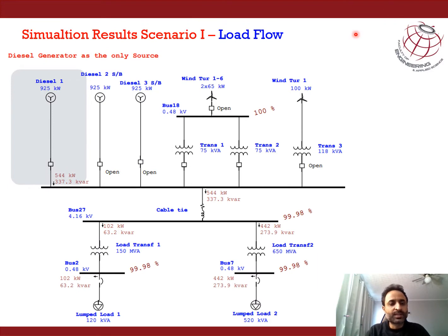So our first scenario is the case when only the diesel generator is running and all other renewable sources are not available. So this was simulated in ETAP by closing the breaker for the diesel generator. The standby diesel generators were open, and you can also see that the wind turbines were also kept open. When the load flow study was run, it can be seen that the diesel generator is able to meet the active and reactive power of the load. 544 is the active power generated, and 337 is the reactive power generated by the diesel. And the results converged, and we can see that at the load we were able to maintain a healthy bus voltage of 99.98%. The required value is 95% or more. So the diesel generator alone can meet the complete load demand of the island of Ramea, even when none of the wind turbines or the new proposed system like hydro is available.